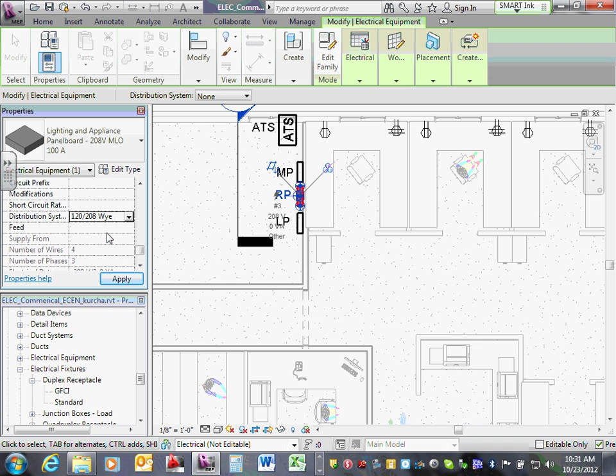What you've told the software is this panel is a 208/120 panel, and it will accept only 208/120 three-phase systems, single phase and three-phase 120. So if you have a piece of equipment that says 480/277, can you circuit it from this? The software is intelligent enough to tell you, are you a knucklehead, these are two different voltages. Everybody got that one?